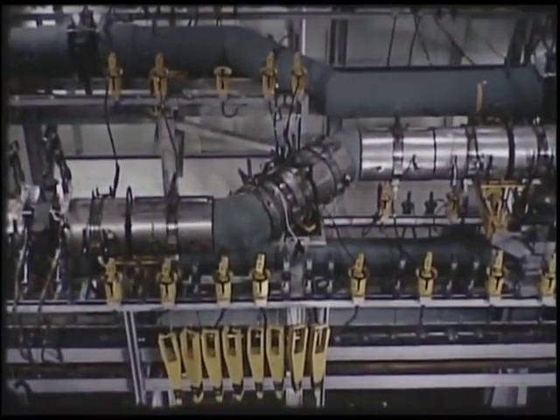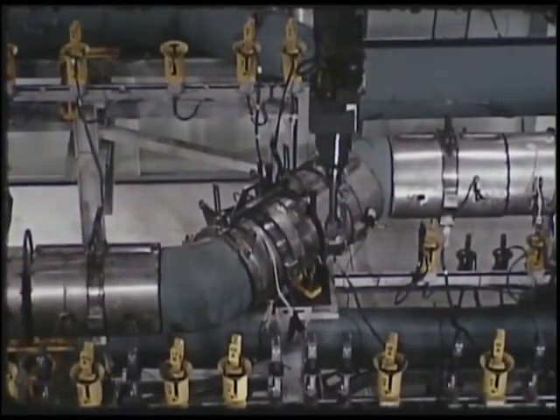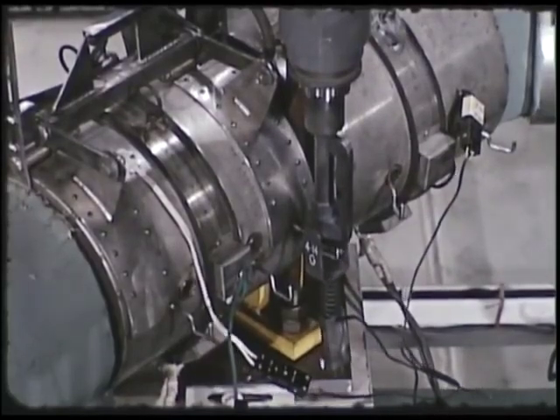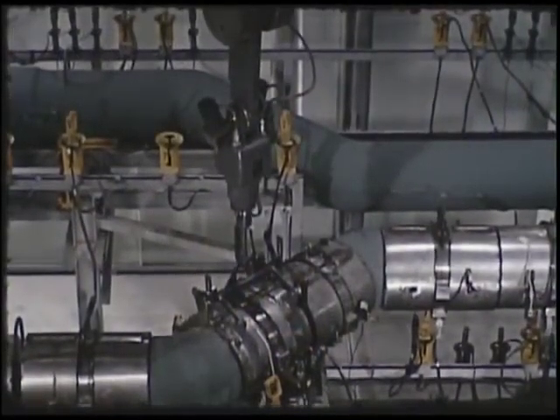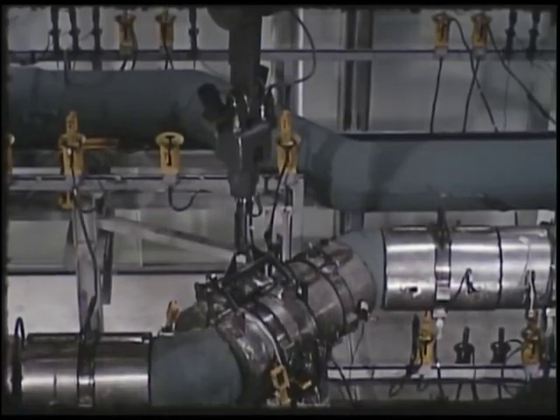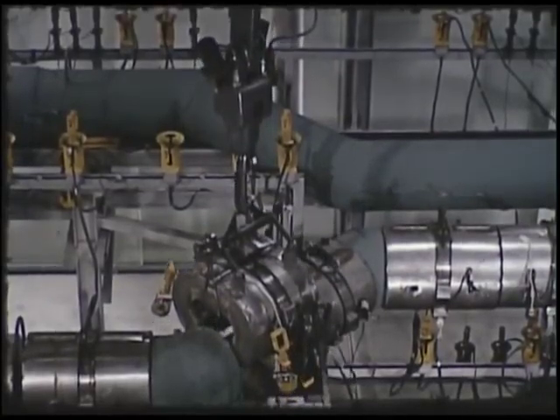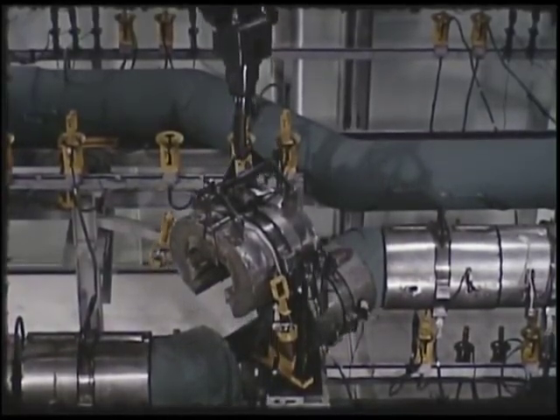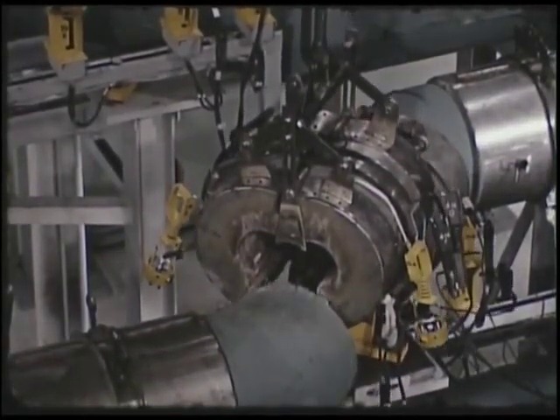Another component designed for remote installation is the electric preheater. These units heat loop piping to 1200 degrees Fahrenheit prior to filling the loop with fuel. The 4 heater and thermocouple leads are disconnected first. As the preheater lifting handle is pulled, the hinged sections spread out and the unit is withdrawn. The replacement heater is then lowered and locked into position by pushing down on the handle.